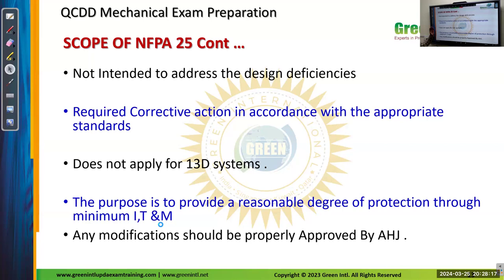It is not intended to address any design deficiencies. In a sense, if you install a fire alarm in this section but you didn't consider the obstruction values of A and B, the purpose of NFPA 25 is not to tell you that this design is wrong or that this installation position is wrong. It will just give you whether the function is working or not. It will not tell you whether the sprinkler system for this room is insufficient, or kept in a wrong position, or that you used a wrong sprinkler system. It will not tell you anything regarding the design. It will give you the functionality, whether whatever you applied there is functioning or not. That is the only function of this NFPA 25.